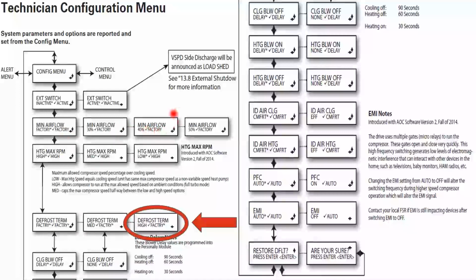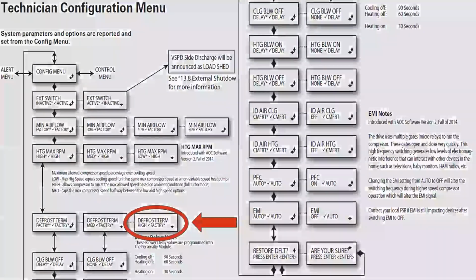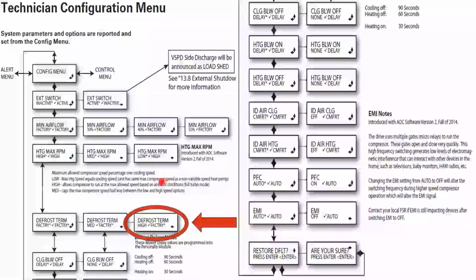So this is going to change the airflow indoor. So if we got a complaint of too low of airflow, we can actually change that minimum airflow to 50%. So we get more air out of the indoor unit, more CFM. Heating max RPM, we usually do not have to change that. Defrost termination. This is one thing we do recommend setting to high in our area.